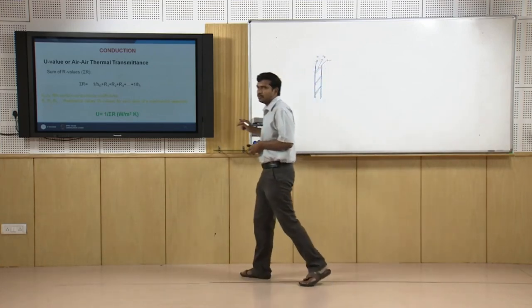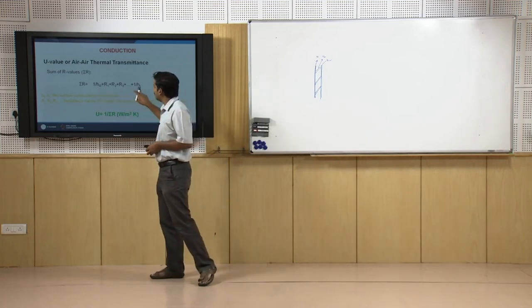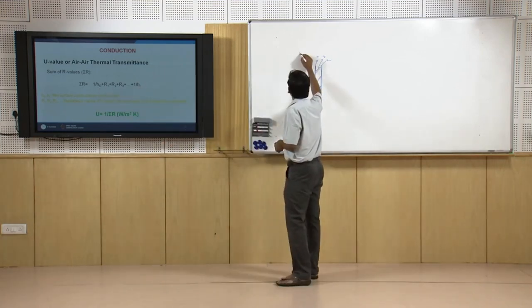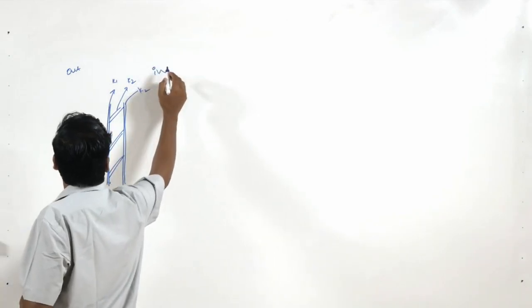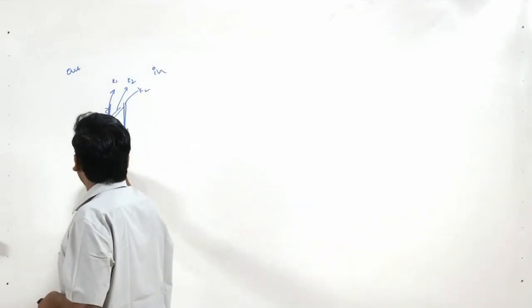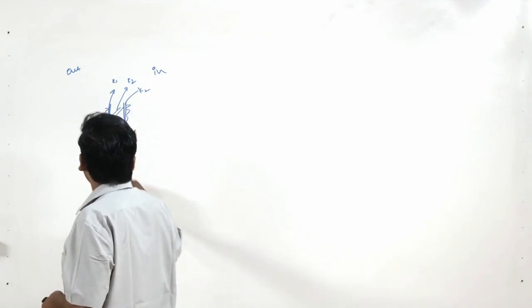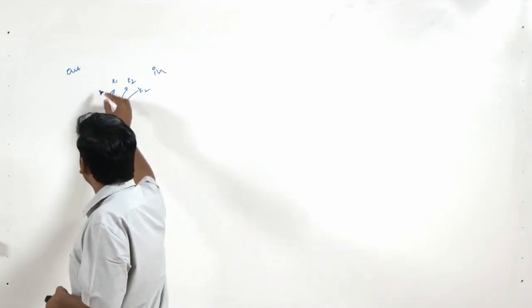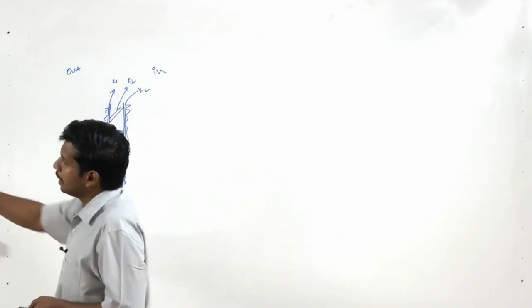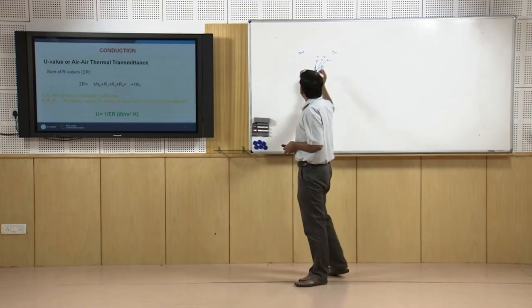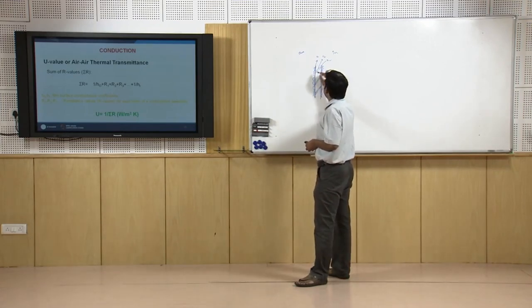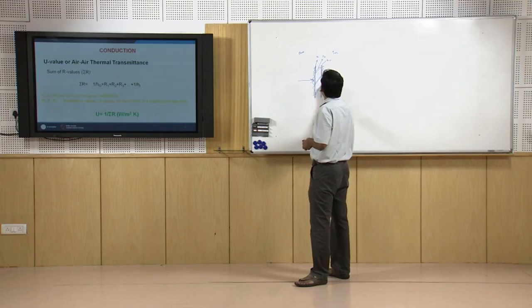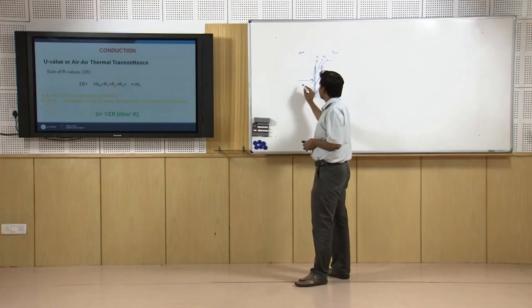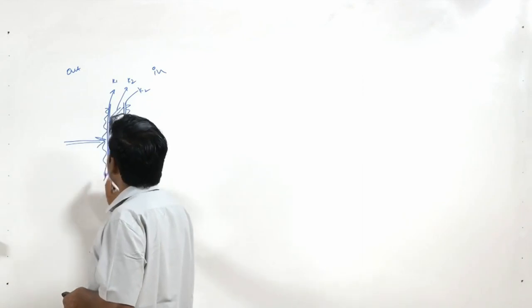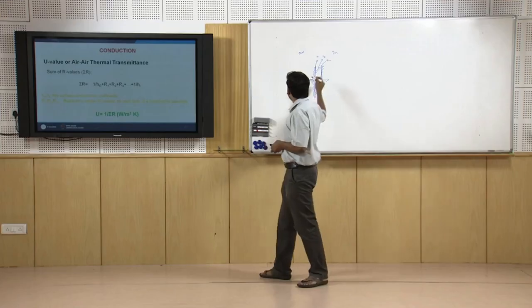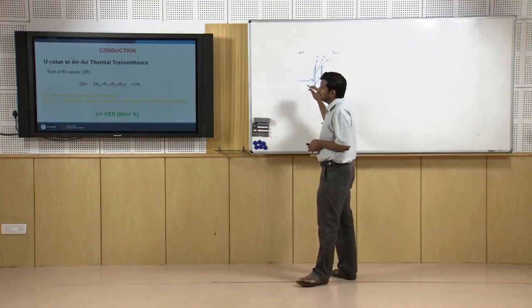But apart from this, there are two other parameters which are here, H0 and HI. If you say this is outside and this is inside, then you have a thin layer of air film which is adhering to this particular surface, both the outside surface as well as the inside surface. Actually, the resistance of this particular film has a quite significant impact on the total conductive heat transfer from outside to inside. This film coefficient primarily depends on the surface characteristics of the wall as well as the environmental condition.